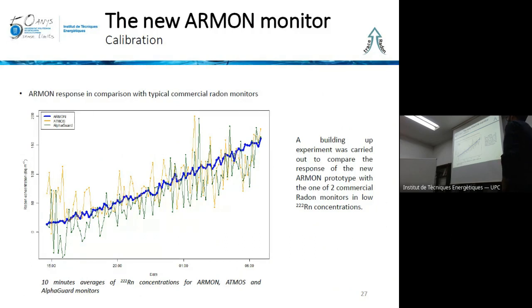We also observed what was happening at low concentrations, and we compared the response of the instrument to two commercial radon monitors. We observed, as we already knew, that the stability of the ARMON was much higher than these other instruments at low concentrations, from 0 to 200 becquerels.